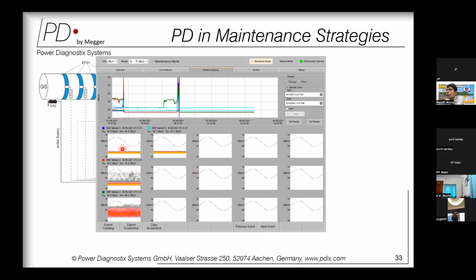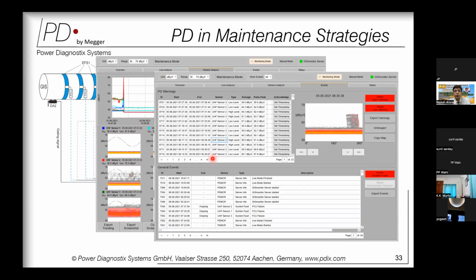That means it can do a spot PD measurement, and it can do trending on all the channels in parallel. Wherever there is a PD, it will record the PRPD patterns, what you expect from any recording device. And it does not stop at recording, because if you have an 8 hour recording, you cannot look out where the PD is occurring. You cannot go through those recordings. You need alarms, which are generated like in an online monitoring system. So this is the next screen. All the sensors are connected in parallel. The system is measuring partial discharge, and the alarms can be set. Whenever these alarms are raised, a PD will be captured and the PD event will be recorded.